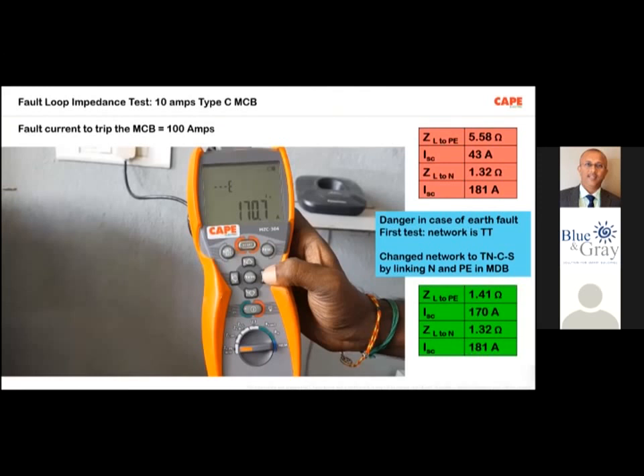So basically, in order to do this particular test, you must understand what the fault protective measures are and what kind of measures you have implemented in your installation, what kind of protective equipotential bonding is made in your installation, what kind of protective devices are there, what the disconnection time is, and then finally, with a meter, we have to do the test.